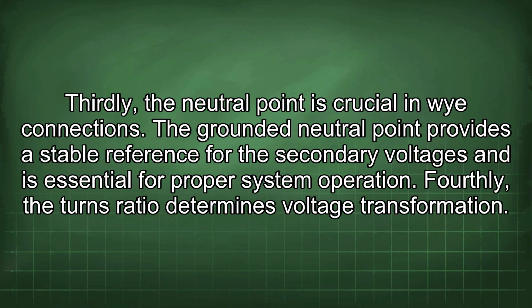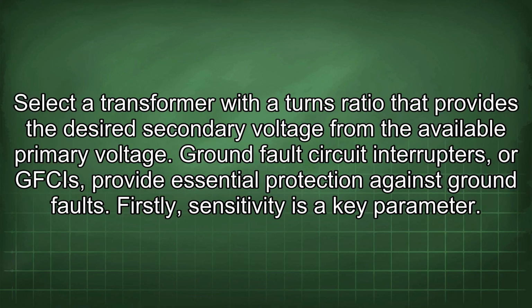Thirdly, the neutral point is crucial in Y connections. The grounded neutral point provides a stable reference for the secondary voltages and is essential for proper system operation. Fourthly, the turns ratio determines voltage transformation. Select a transformer with a turns ratio that provides the desired secondary voltage from the available primary voltage.